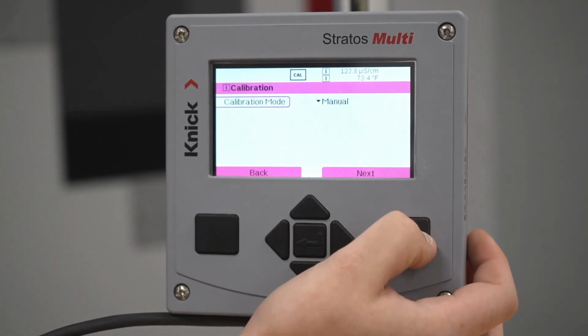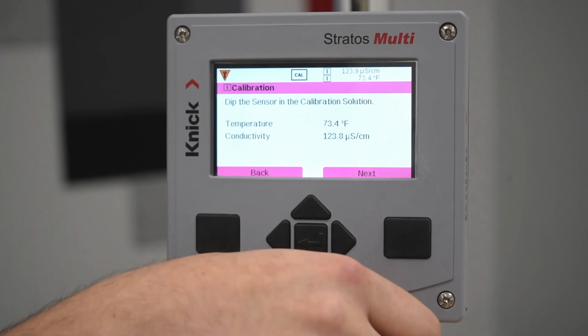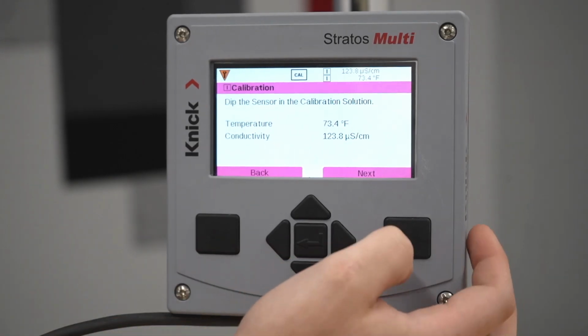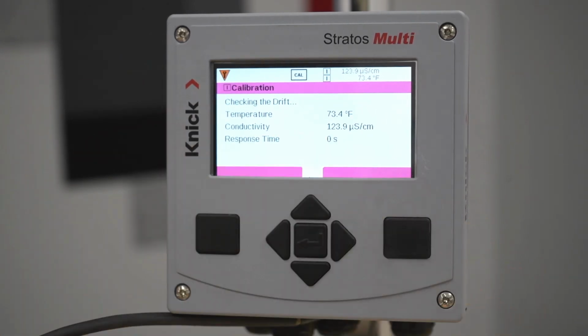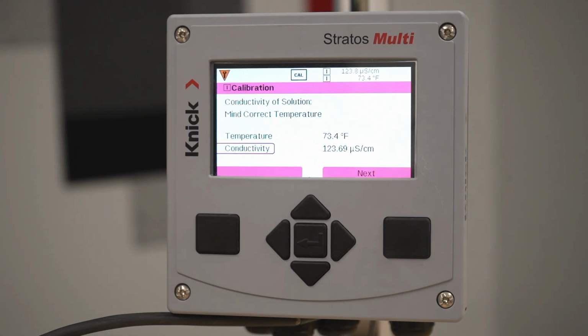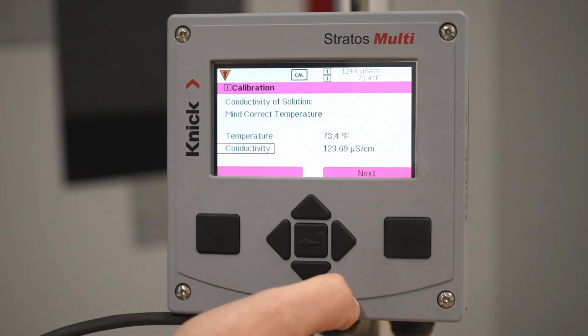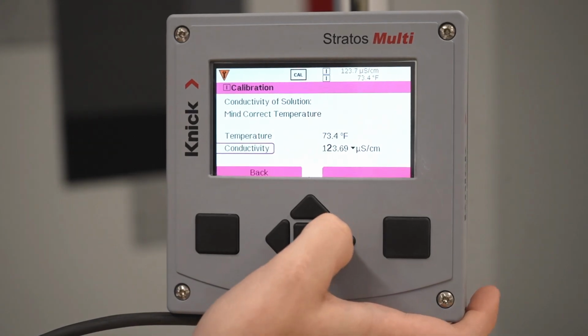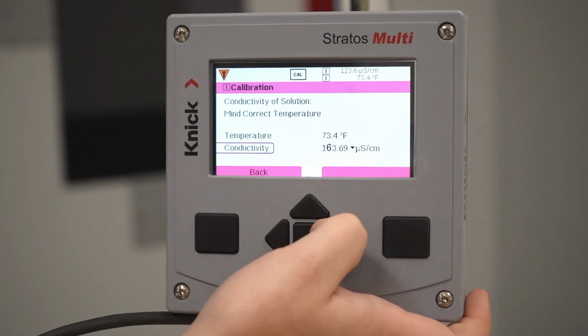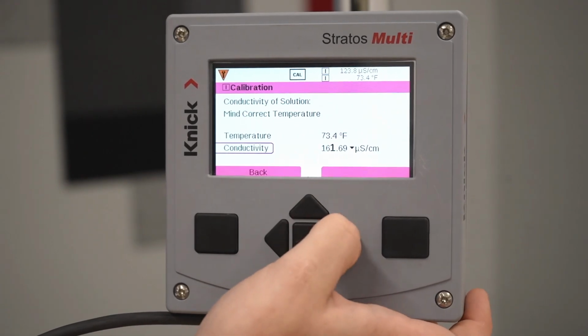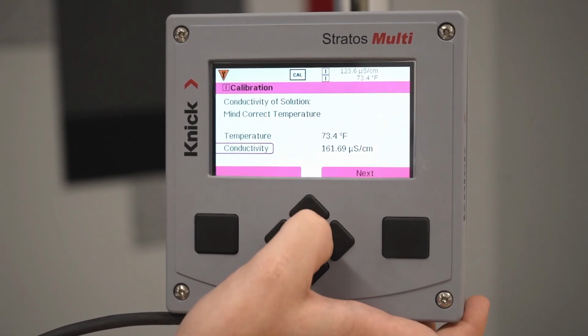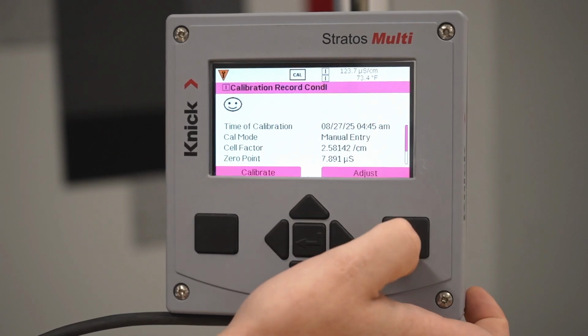To start this, we're just going to press next. And then since it's already been sitting in the conductivity standard and it's leveled out, I can go ahead and move on and allow it to take the sample. And then we'll also see we're at 73.4 degrees. So that puts us at right around 161 microsiemens. So I'm going to scroll over, and now we're just going to change the read value to what our conductivity buffer is at this temperature. Pressing enter once I'm done, and then next.